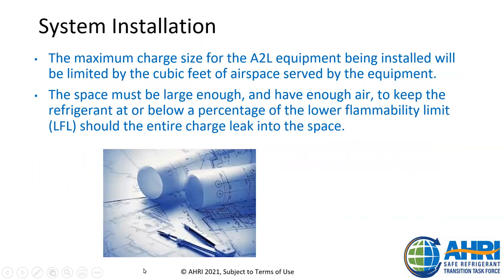The maximum charge size for A2L equipment being installed will be limited by the cubic feet of airspace served by the equipment. The space must be large enough and have enough air to keep the refrigerant at or below a percentage of the lower flammability limit, or LFL, should the entire charge leak into the space. The maximum allowable charge is not a universal figure, and it will be different for every system installation and occupancy classification. The information has been thoroughly researched and has been laid out in the updated industry standards. To cover those codes and standards and how they function, I will now turn it over to my colleague, Anuj. Anuj, over to you.